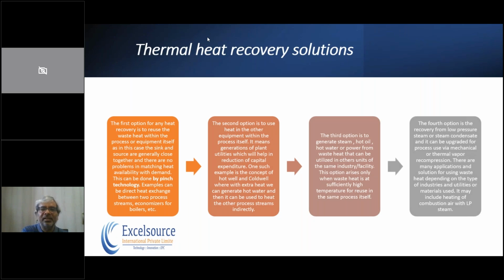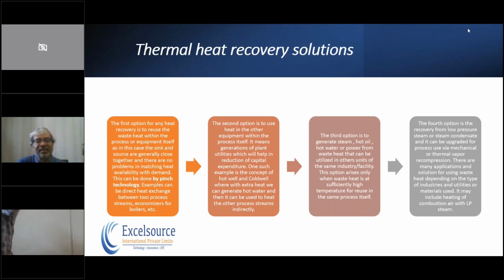So how do thermal heat recovery solutions help us? The first option is to recover the heat in a way that it can be utilized within particular sections of the plant itself, so that we don't take the waste heat to different sections and make the plant more uneconomical. An example within the systems is boilers where economizers are installed. Economizers can be water economizers, steam water economizers, or air flue gas economizers.